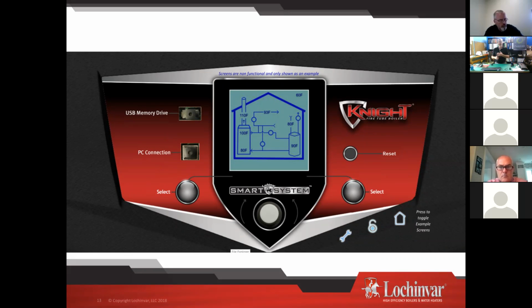What's my system temperature? What's my outdoor temperature? You get to see everything all at once. It's just definitely a good troubleshooting screen sometimes. Somebody says, hey, it's just not warm enough. I don't think I have heat. And you come down here and you say, geez, I've got water coming out of the boiler at 180 degrees, and I've got a system sensor that says it's 70 degrees. Could be a problem right there. You know, we could have a distribution problem. So definitely some good stuff to look at on that screen right there.